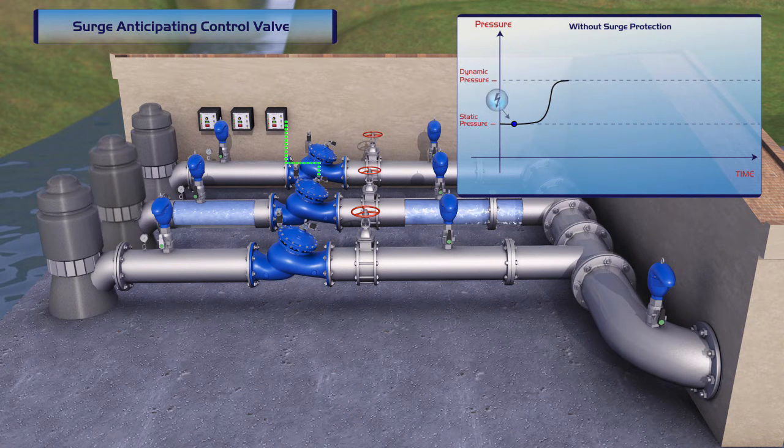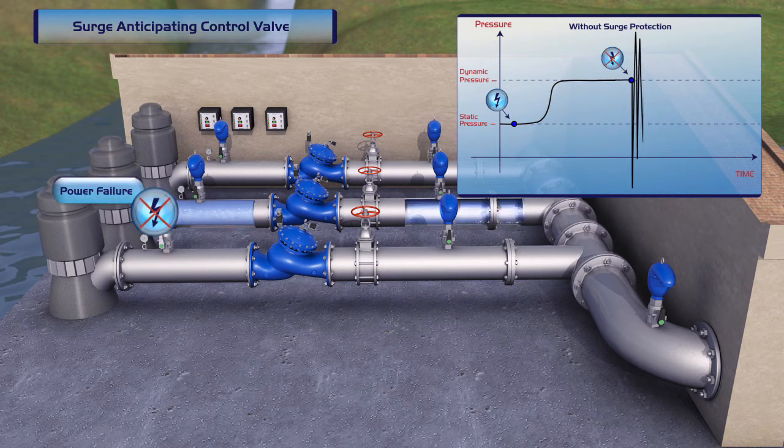However, depending on system topography, additional protection against severe surge and water hammer damage is required, as shown on the chart. This can be achieved by installing one of Bermad's surge-anticipating valves. Among the available options is the Bermad Offline Hydraulic Surge Anticipating Valve, which senses line pressure and remains closed during regular operation of the system.